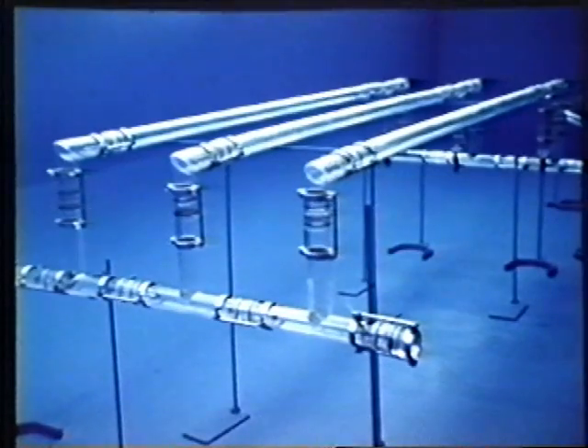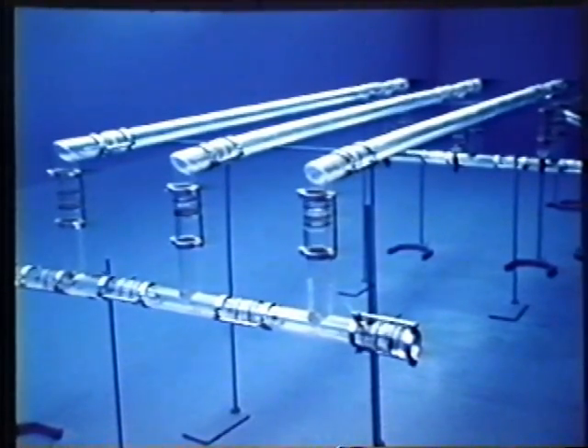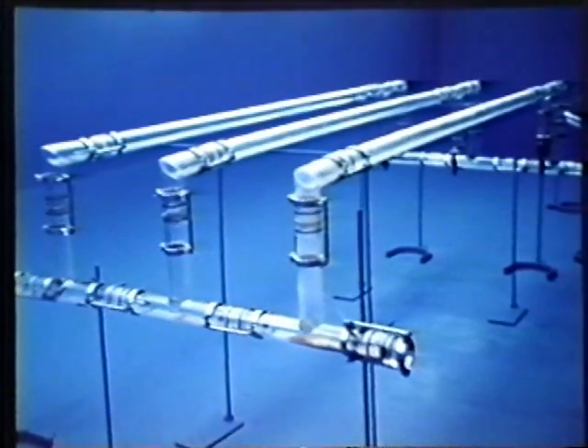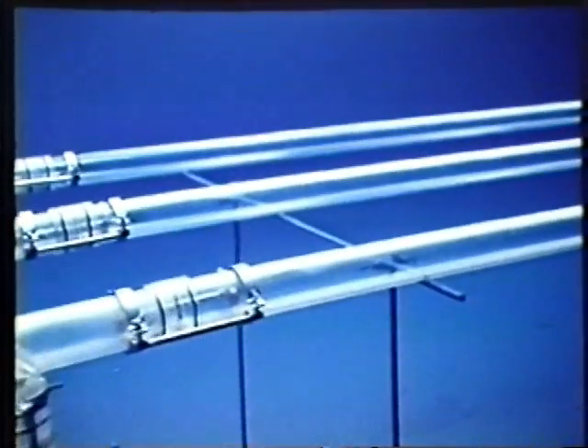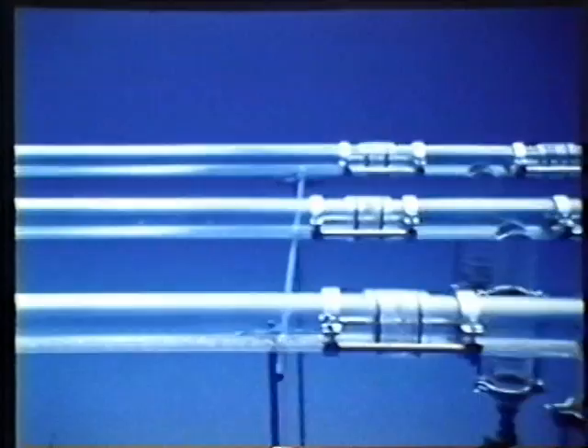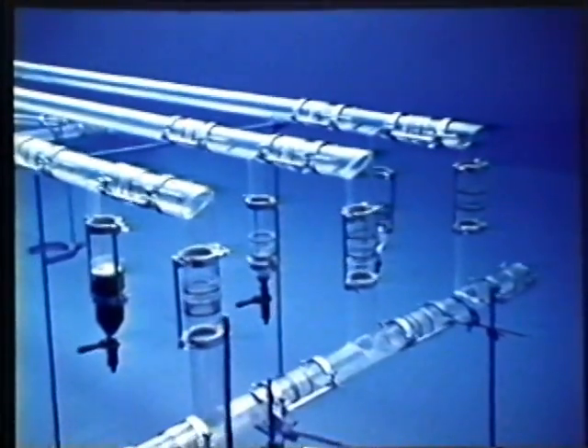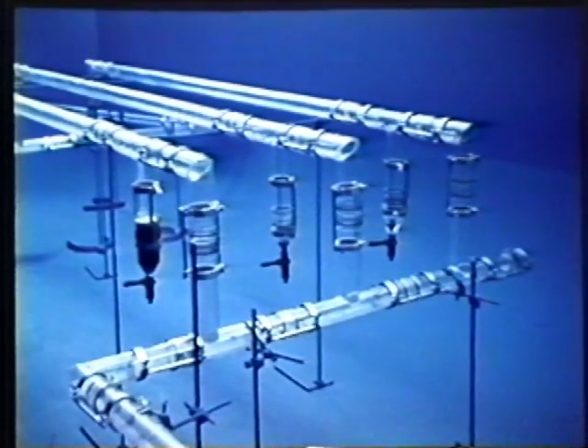This is the pipeline situation at the inlet side of a gas delivery station. The gas comes from the left and divides over the meter runs. It appears that the liquid carried along accumulates at the last meter run. The liquid separator in this particular meter run is already half filled, while the liquid traps in the other two runs are still practically empty. The separator in this meter run must therefore be designed to handle all the liquid.